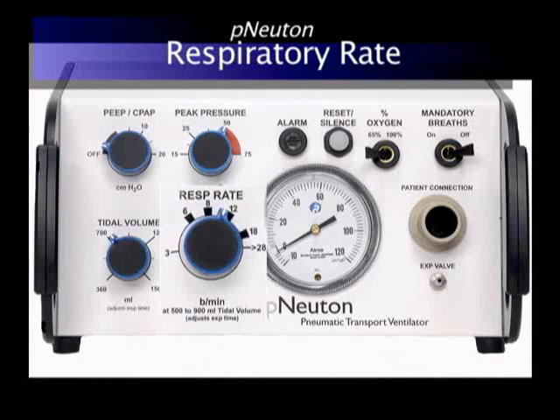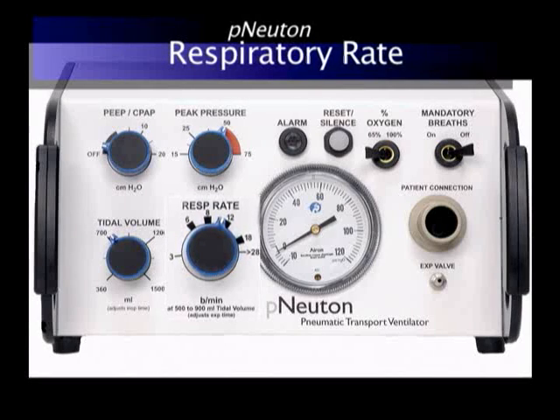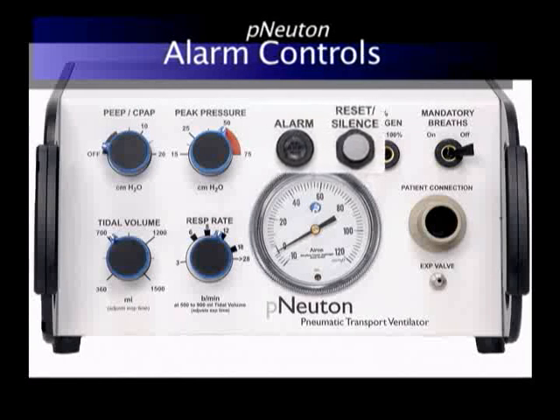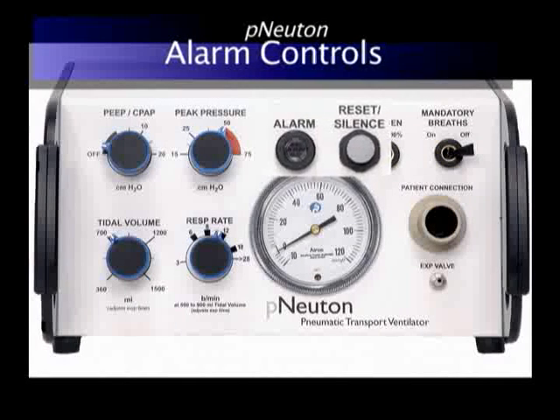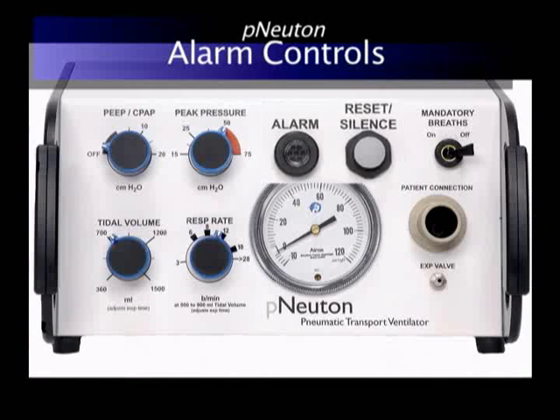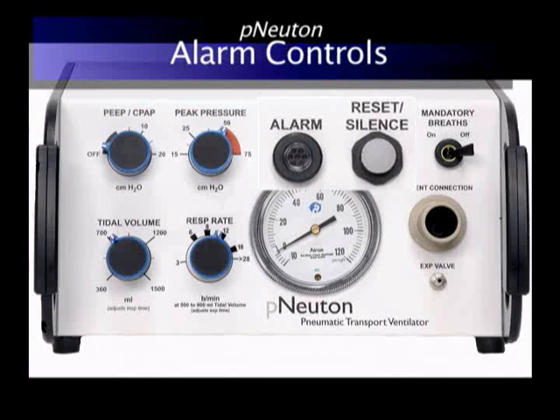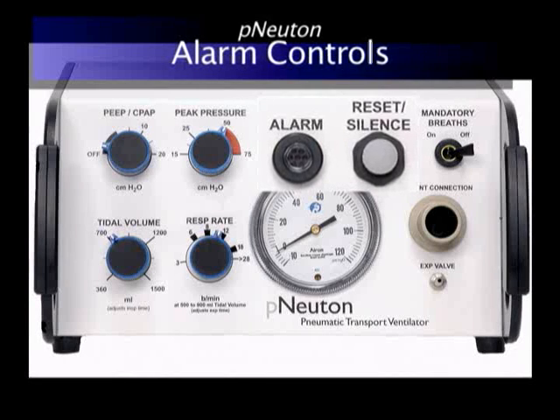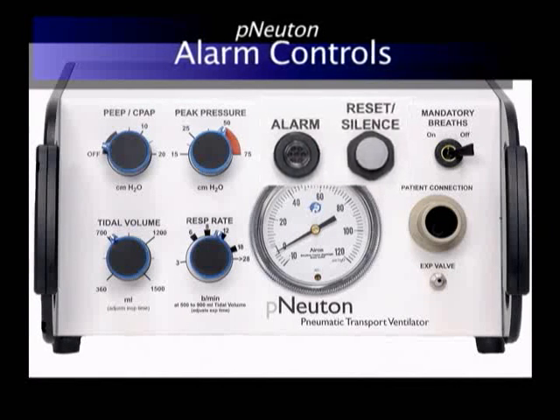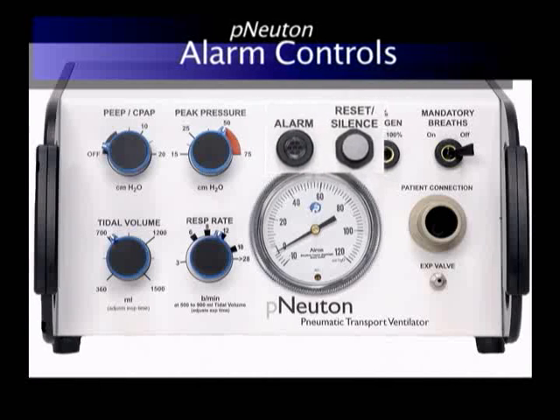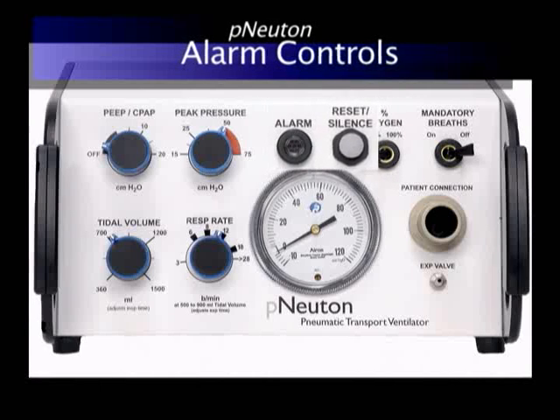The patient mandatory breath rate control has a range of 3 to greater than 28 breaths per minute. The control has a wider range at lower respiratory rates to provide better control for slower IMV rates. Patient respiratory rates should always be monitored to ensure adequate ventilation. The alarm controls include the alarm visual indicator and the alarm reset/silence. The alarm reset silences the alarm for one minute, and the alert condition is activated when a patient disconnect has occurred or when low source gas pressure is detected.